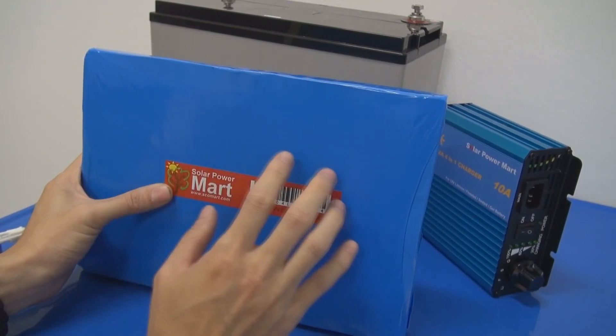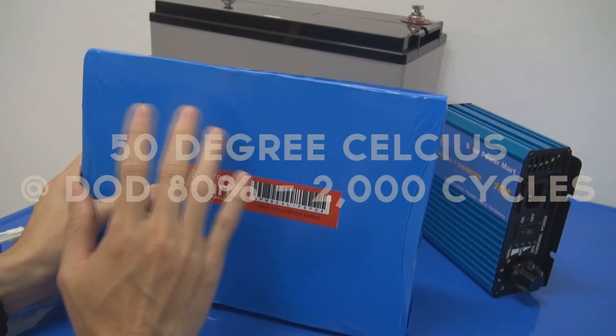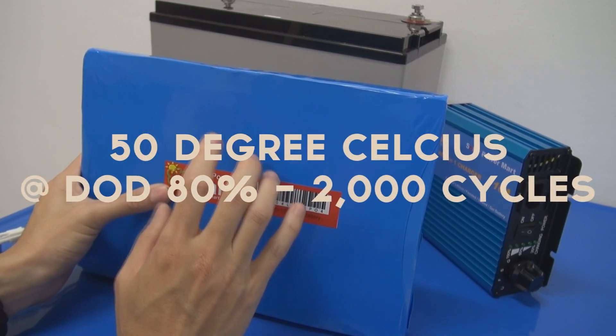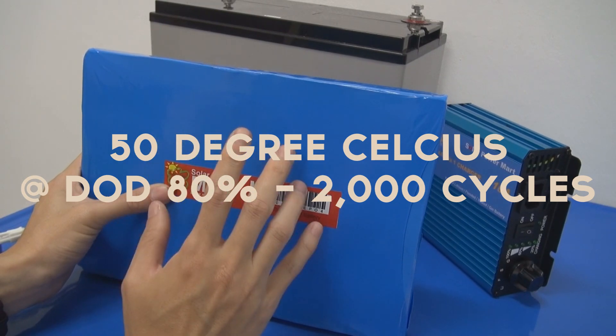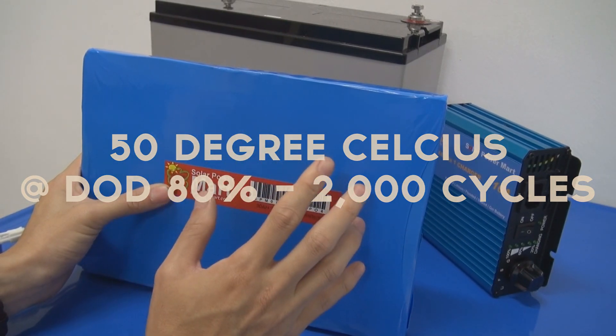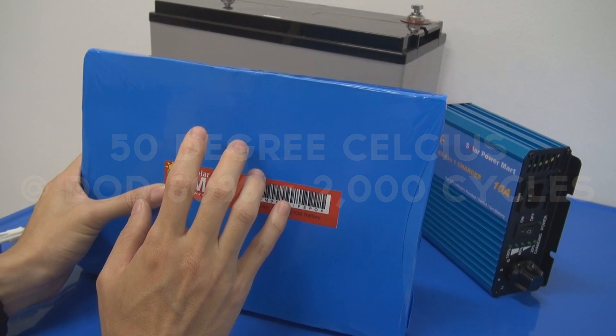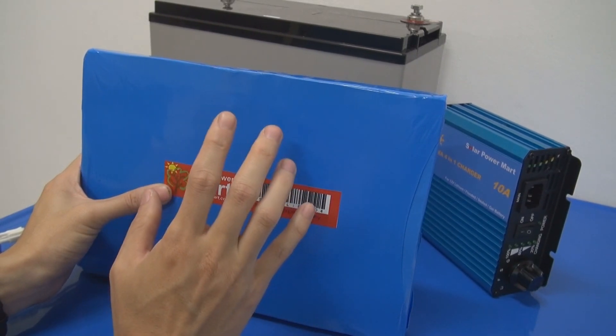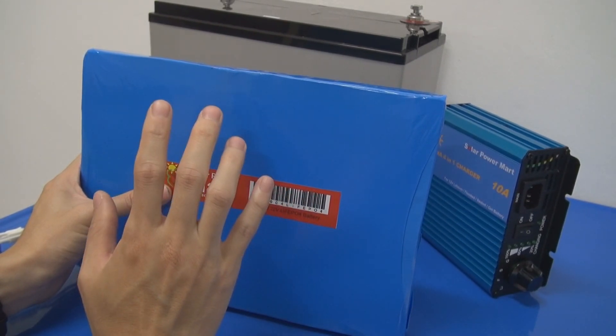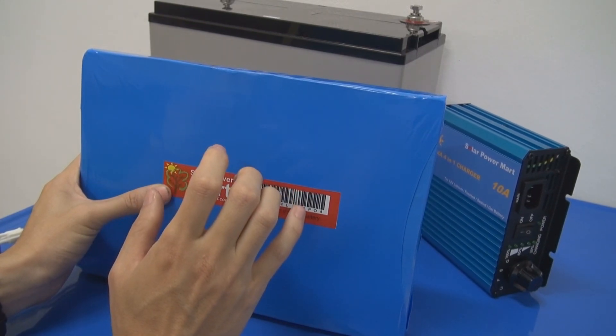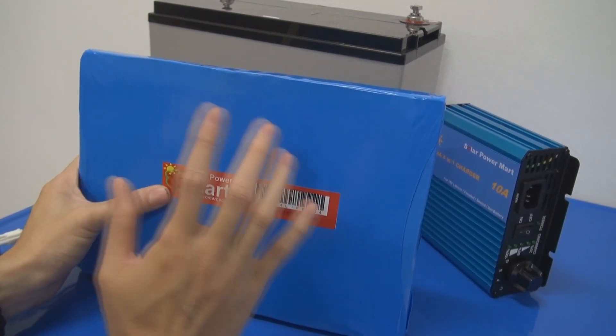So even if you use this battery at roughly around 50C and do a DoD of 80%, it still will give you 2,000 cycles. In other words, more than five years. So one thing good about lithium battery is it's very good with temperature. That means it performs very well in hot conditions.